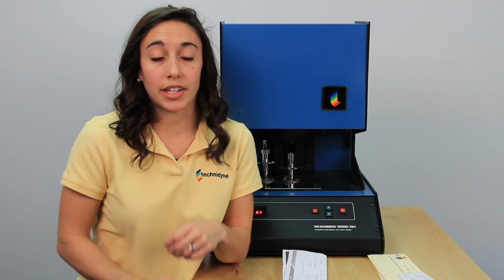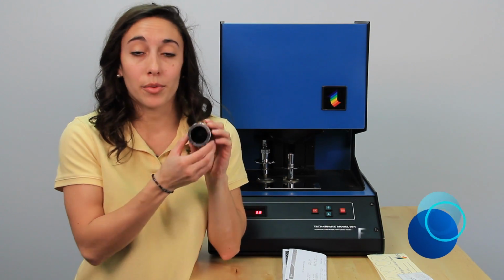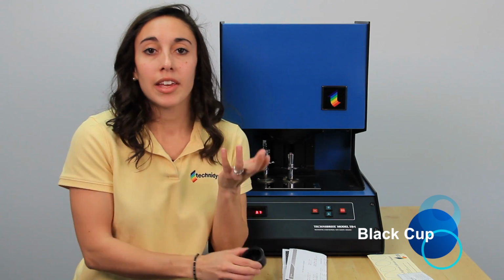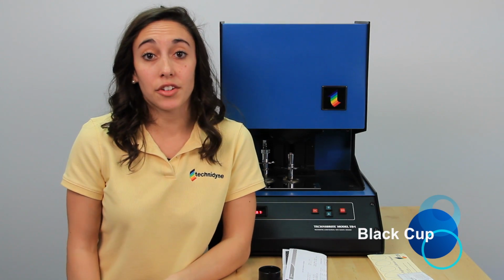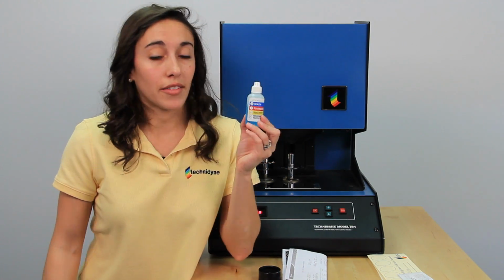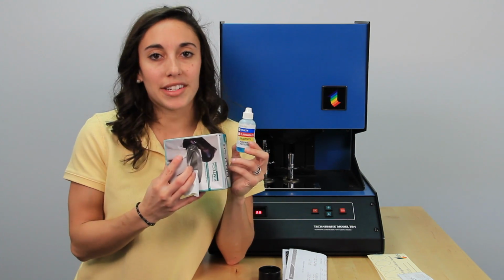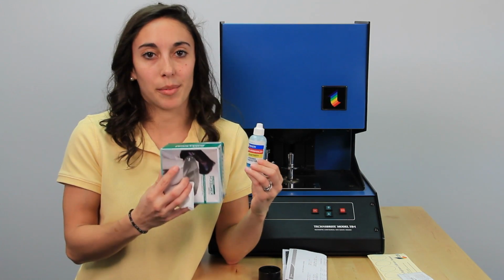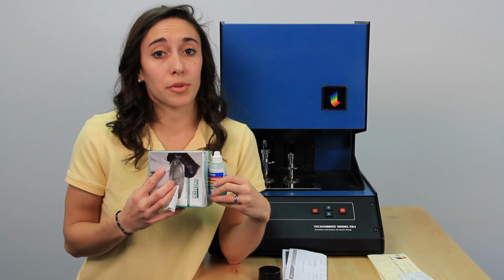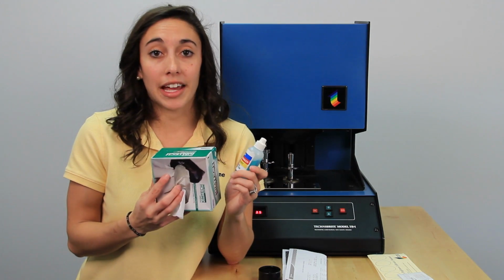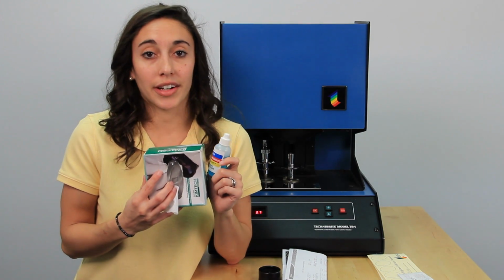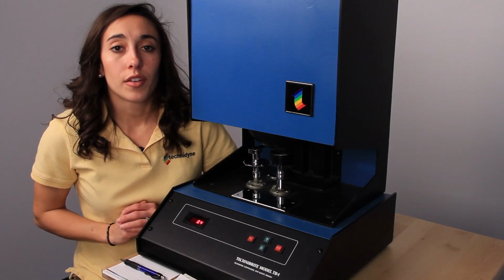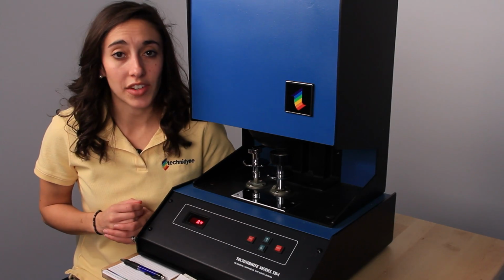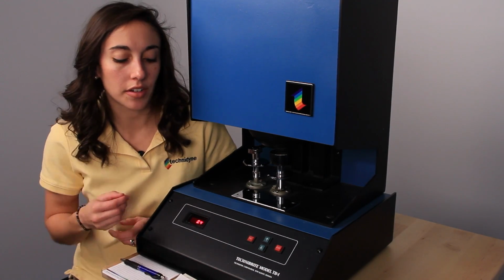In addition to those things, you'll also need the black cup, which came with your instrument. And just to make sure that your swing-in standard stays clean, we suggest that you have a cleaning solution and a non-abrasive, non-optically brightened cleaning wipe on hand. Once your instrument is warmed up and you have everything together, we're ready to go ahead and get started with our calibration. For our first step, we'll need the 70 standard, which is our primary standard.